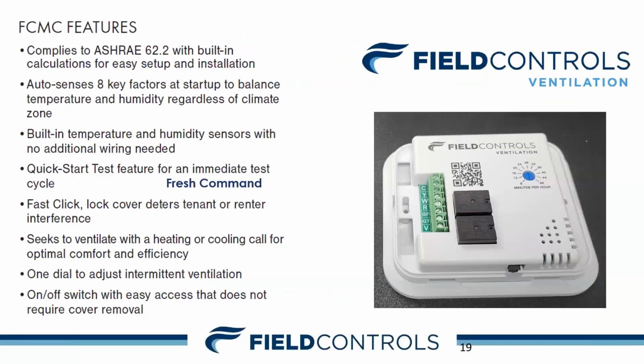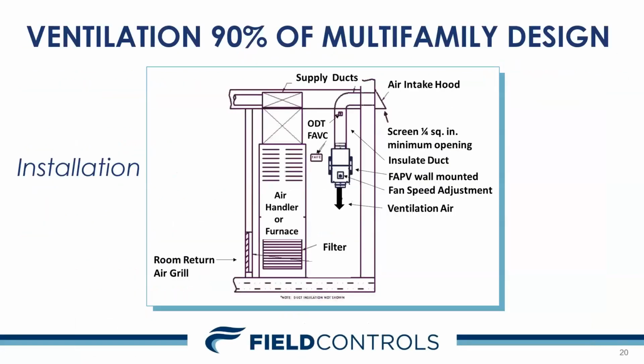Speaking to more of a mixed utility setup, I'm actually going to skip ahead here. What we see in 90% of multifamily design is a utility closet that brings in outside air through a ventilator or through a mechanical damper, mixes into the air handler, and then disperses from there. Primarily, when you take a control and mount it in the utility closet, remember the example I used prior. If you're using a ventilating thermostat, often it's too late for that thermostat to recognize what's happening in the environment. So we've seen multiple properties with issues inside of the utility closet that create damp environments, mold, mildew, as well as just a funky smell that disperses throughout the complex.